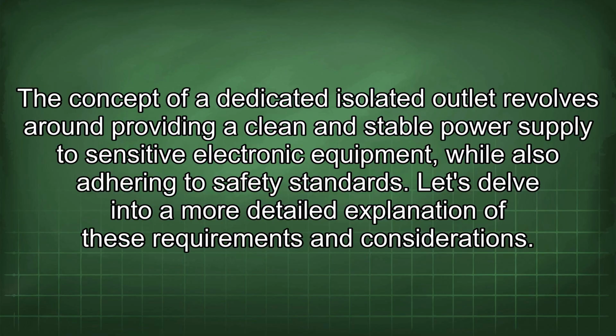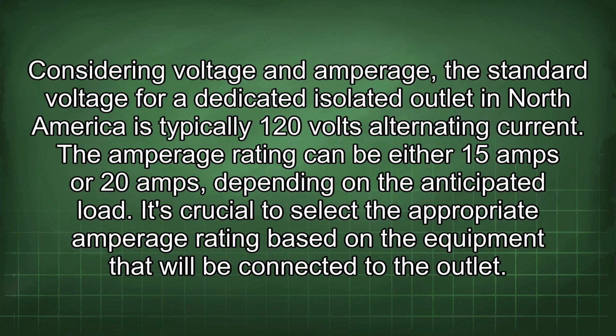The concept of a dedicated isolated outlet revolves around providing a clean and stable power supply to sensitive electronic equipment, while also adhering to safety standards. Let's delve into a more detailed explanation of these requirements and considerations. Considering voltage and amperage, the standard voltage for a dedicated isolated outlet in North America is typically 120 volts alternating current. The amperage rating can be either 15 amps or 20 amps, depending on the anticipated load.